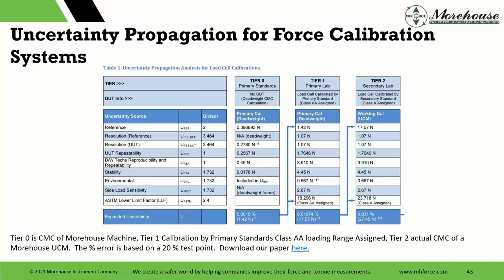And this is from that paper, and there's the link from the paper. But if we're looking at things, we're looking at our reference standard, the resolution of the reference, the resolution of the unit under test, the UUT repeatability. I want to test my techs. I don't know what technician's going to see an instrument. I can't always assign it to Tanner, the best guy in the room right here, or Patrick. I need to go on and get what happens if Joe does it, or Bob does it, or Sally does it. All this. So I really should be doing R&R between techs to see if there's a statistical difference between any of my techs.